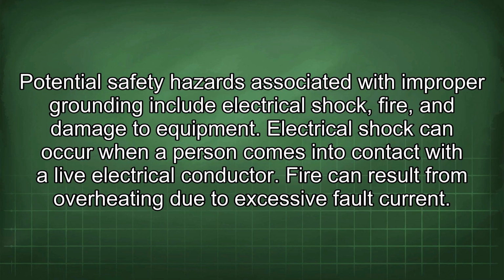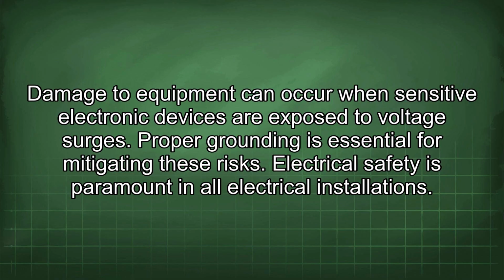Potential safety hazards associated with improper grounding include electrical shock, fire, and damage to equipment. Electrical shock can occur when a person comes into contact with a live electrical conductor. Fire can result from overheating due to excessive fault current. Damage to equipment can occur when sensitive electronic devices are exposed to voltage surges. Proper grounding is essential for mitigating these risks.